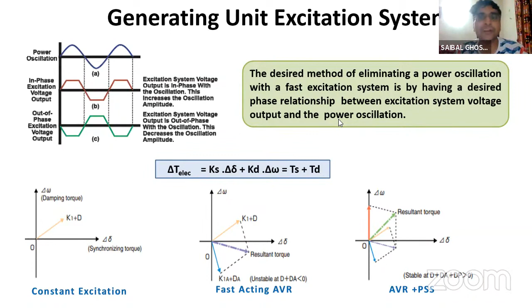So you can see that whenever there is a sudden change in the excitation system, the generator electrical power also changes. Why? Because the flux remains almost the same. Flux does not change immediately like the voltage, and we know from the equation that the power output is V1 V2 by X sine delta. Delta is fixed, everything is fixed, and suddenly V is changing, so the power output changes. But eventually delta changes when you change the excitation, and the power output comes back to the original value. It cannot give you a sustained response or increase in generation. A sustained increase in generation is not possible without any mechanical input, but it can cause a momentary change in the electrical output.